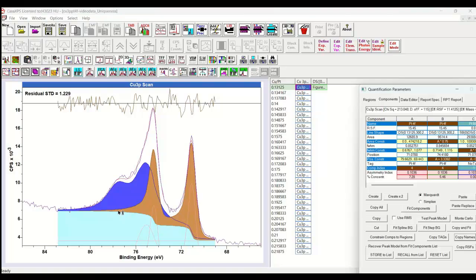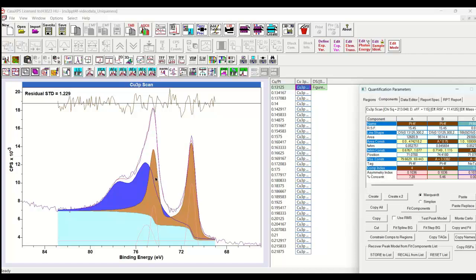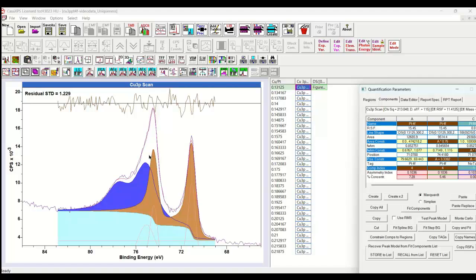So this example is demonstrating that the background and the line shapes alter as a function of the line shapes or putting it another way the line shapes alter as a function of the background. So when we choose a Shirley background and we force a line shape to then match that Shirley background the Shirley background has determined the asymmetry for the line shape. Now that may be what you'd like in terms of reproducibility but it's not necessarily the same as saying that the line shapes or the peak model are physically meaningful with respect to the sample and the data that we've collected.